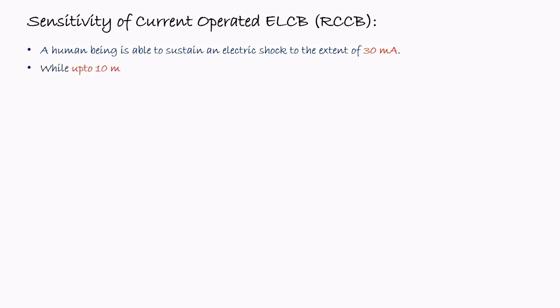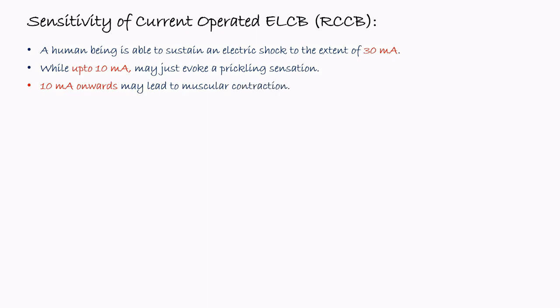The sensitivity of the current operated ELCB or RCCB is very important for living things, from electrical shock. Basically a human being is able to sustain an electrical shock to the extent of 30 milliampere, while up to 10 milliampere it may just evoke a prickling sensation. So up to 10 milliampere there will be some sensation in the body of the human or any animal. From 10 milliampere onwards it may lead to muscular contraction. So the sensation will increase and there will be more problems in the human body, further leading to respiratory paralysis at around 30 milliampere. So if the current flowing through a human body is almost equal to 30 milliampere or more than 30 milliampere, it will be a fatal condition.